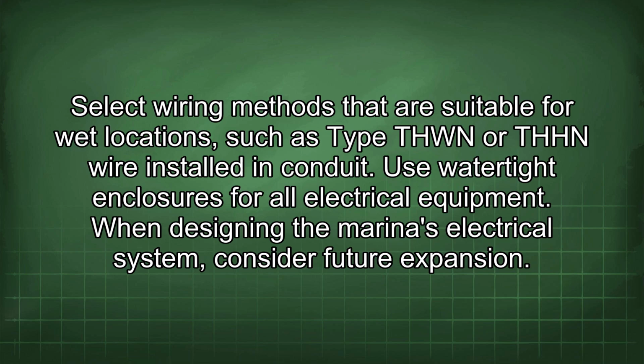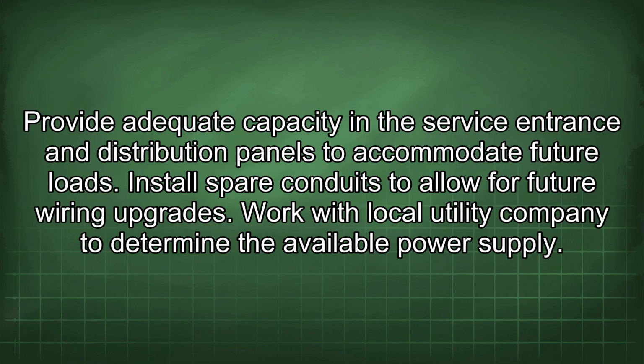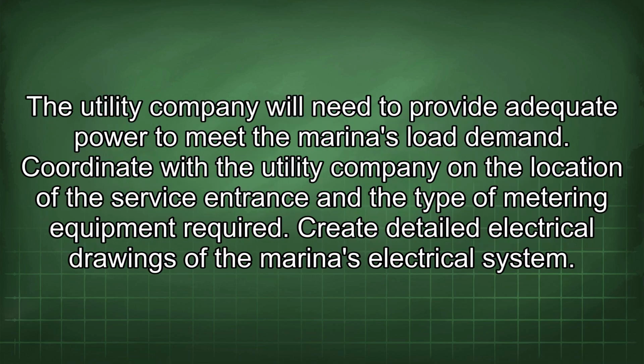When designing the marina's electrical system, consider future expansion. Provide adequate capacity in the service entrance and distribution panels to accommodate future loads. Install spare conduits to allow for future wiring upgrades. Work with the local utility company to determine the available power supply. The utility company will need to provide adequate power to meet the marina's load demand. Coordinate with the utility company on the location of the service entrance and the type of metering equipment required.